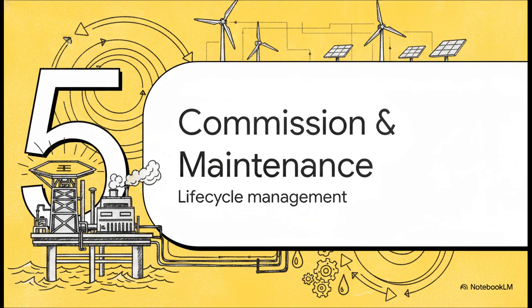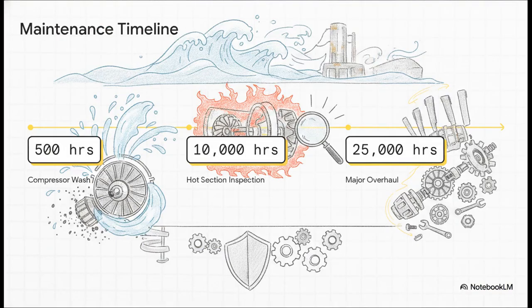Finally, let's wrap up with Part 5, Commissioning and Maintenance Recap. Remember that heavy 5% dirty engine penalty we just talked about? Your absolute best defense against that is the routine compressor wash, scheduled every 500 to 1,000 hours. Seriously, this is non-negotiable for offshore survival. Further down the line, you're looking at comprehensive hot section inspections around 8,000 to 12,000 hours, and a massive, complete major overhaul when you hit that 25,000 to 50,000 hour mark. The harsh environment is constantly trying to destroy this machine. Maintenance is simply how we fight back.